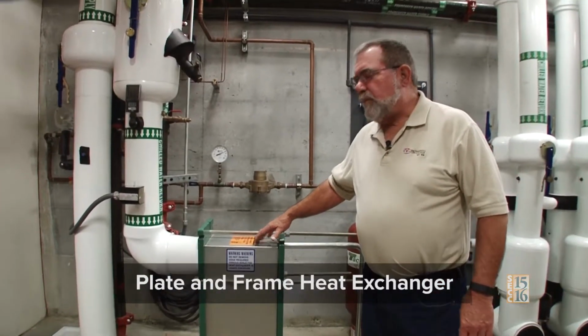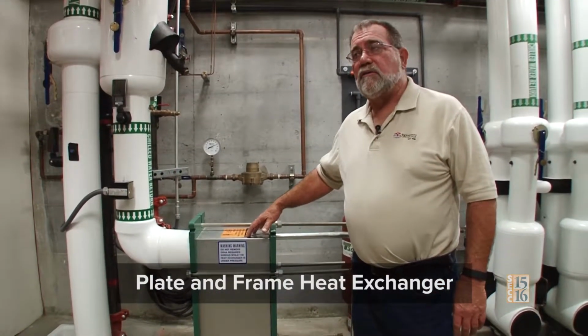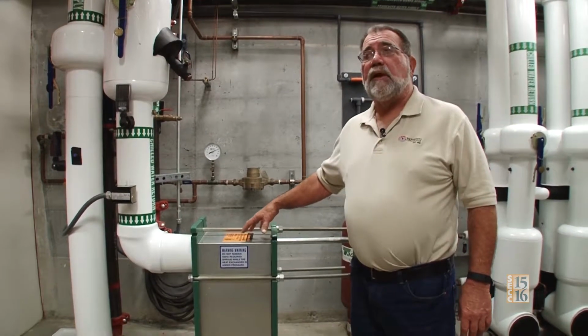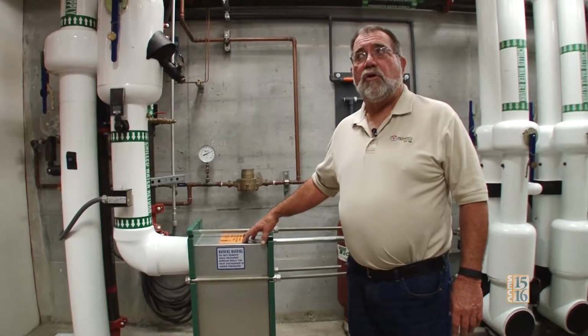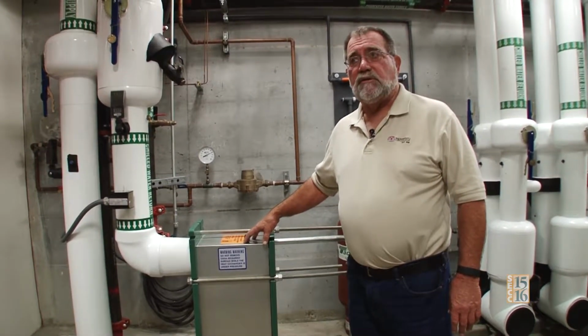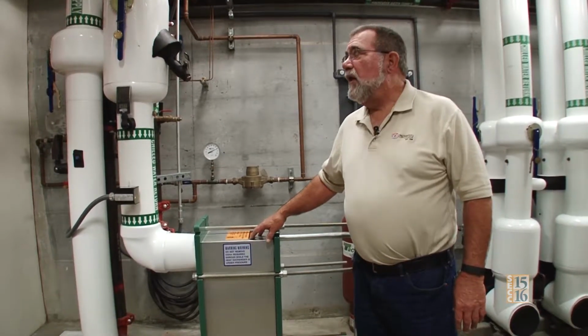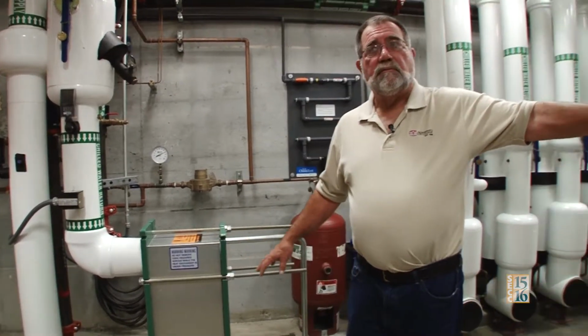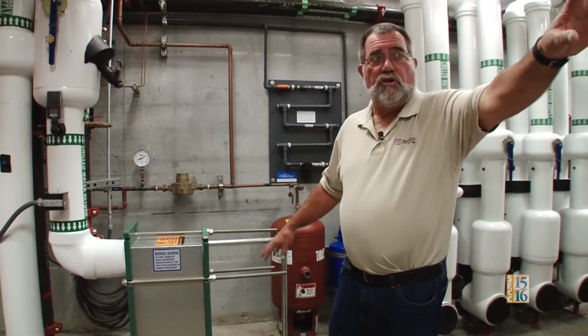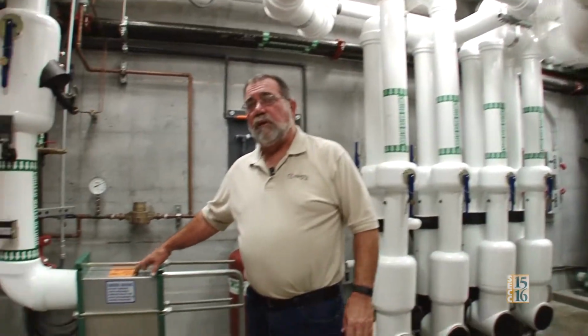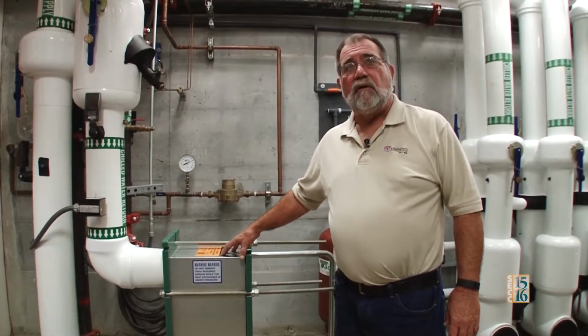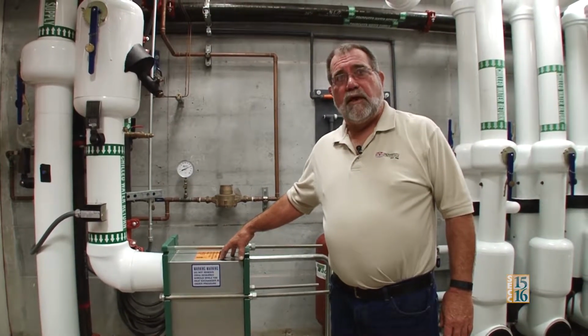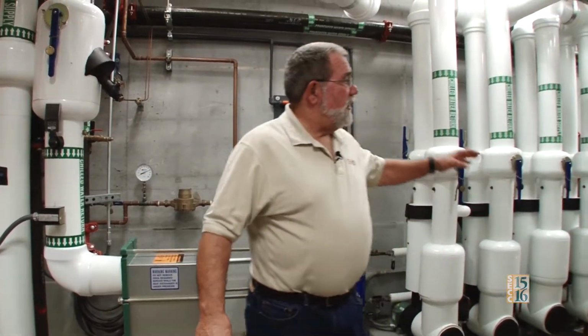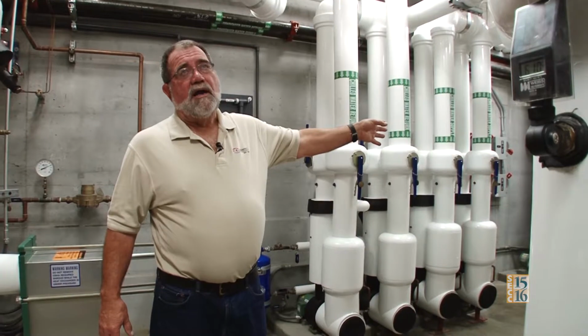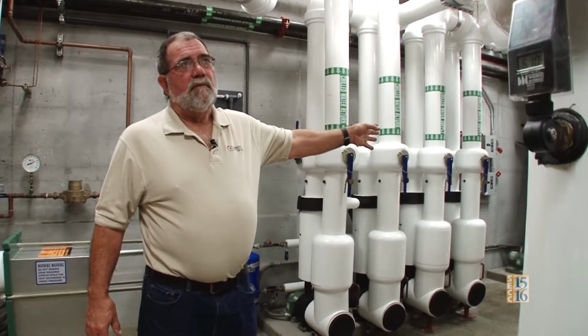We have a plate and frame heat exchanger, so we have three methods of cooling our buildings other than outside air: we can use the chiller to cool the chill water, we can use the plate and frame with the cooling tower on cooler days, or we can use our ice bank to cool the water.